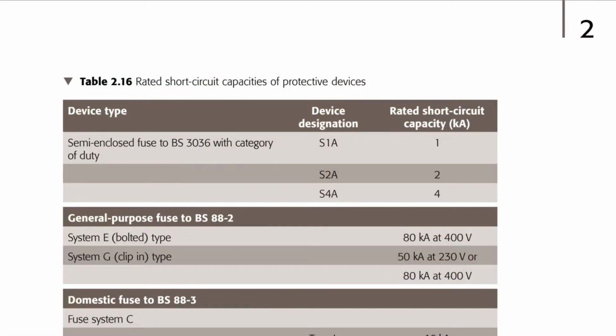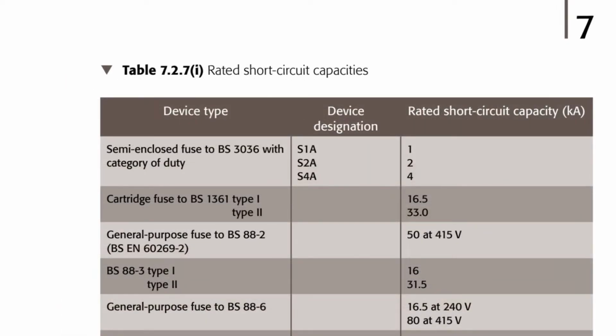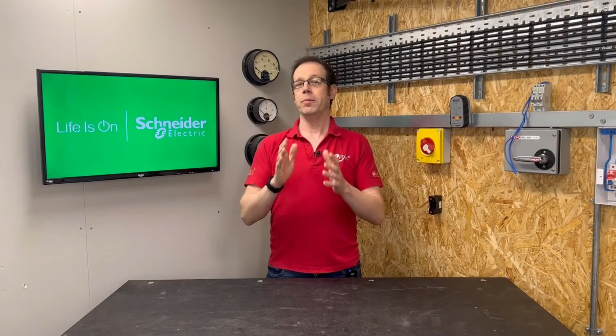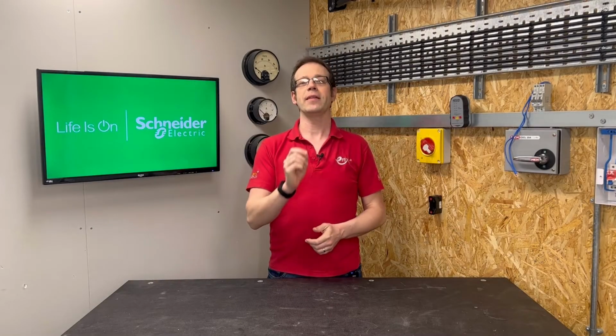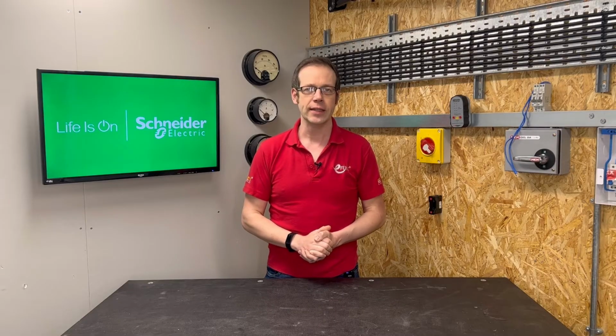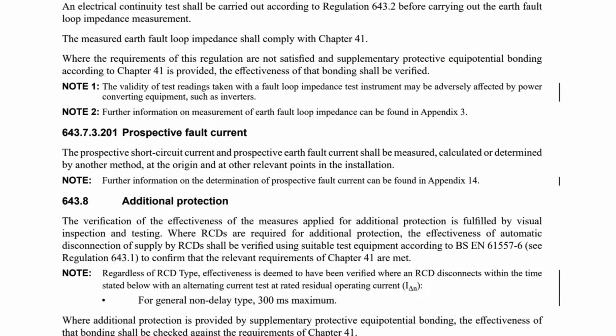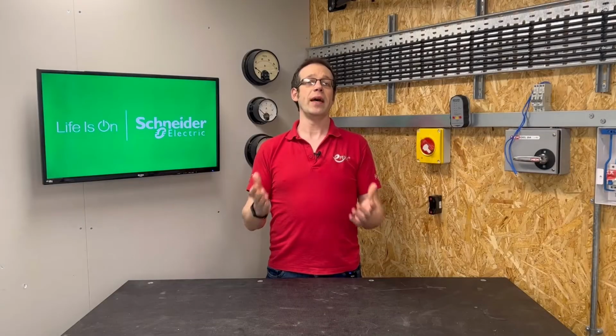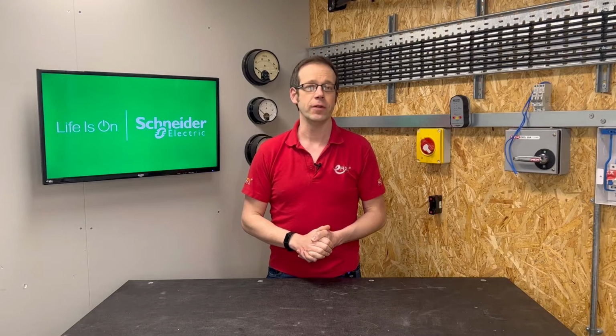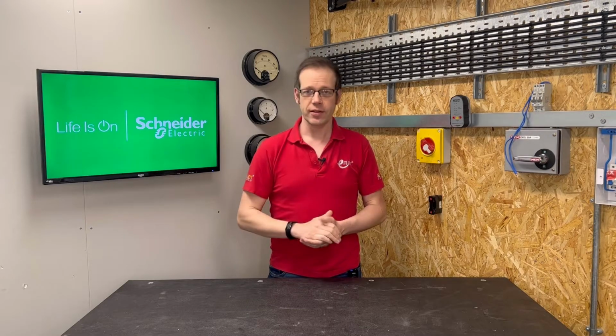Well, BS 7671 does not include a definition to explain this, but Table 2.16 of Guidance Note 3 and Table 7.2.7(I) of the On-Site Guide both have details regarding what ICN is all about. As stated in both of these publications, we're looking at the prospective fault current ratings of our circuit breakers. Regulation 643.7.3.201 says we need to look at the current that may flow in the event of a short circuit at every relevant point of the installation, which means every point where a protective device is required to operate under fault conditions, and includes the origin of the installation.